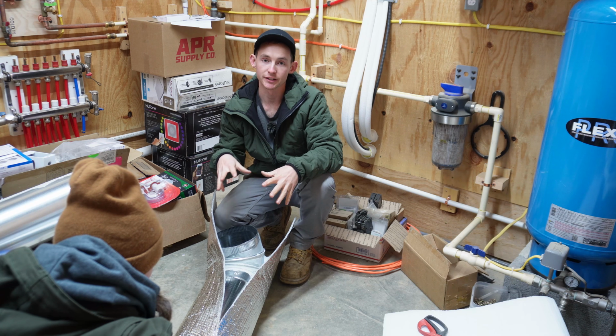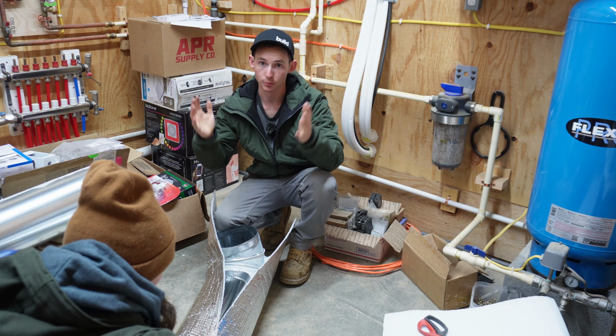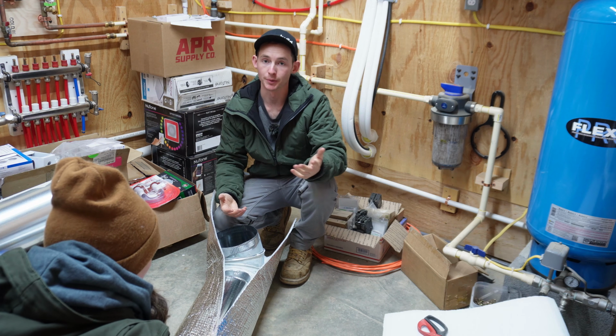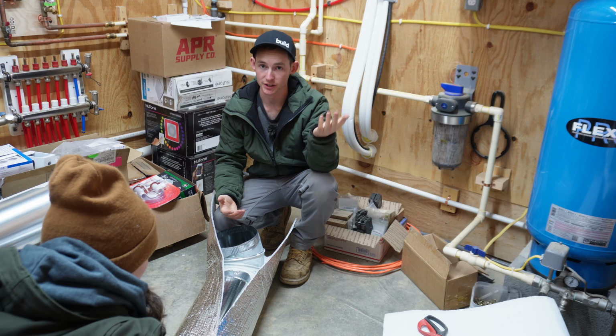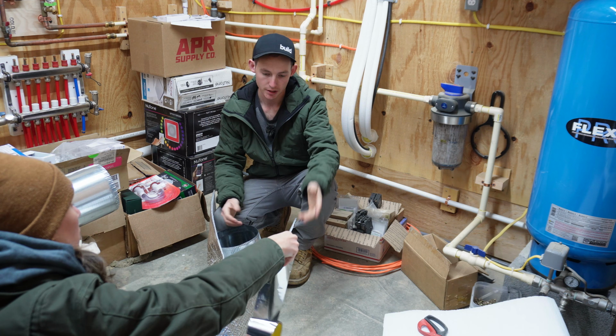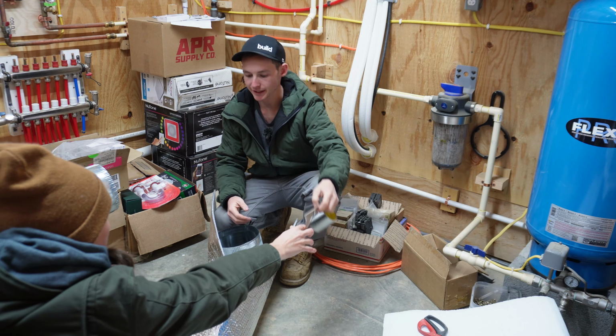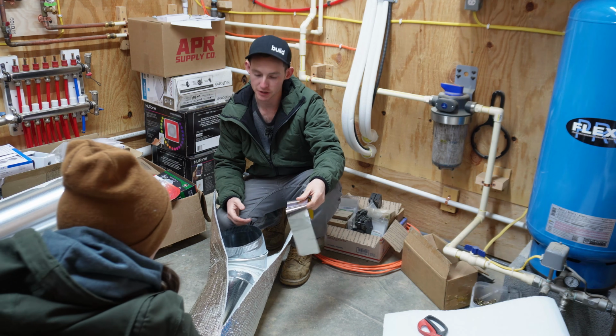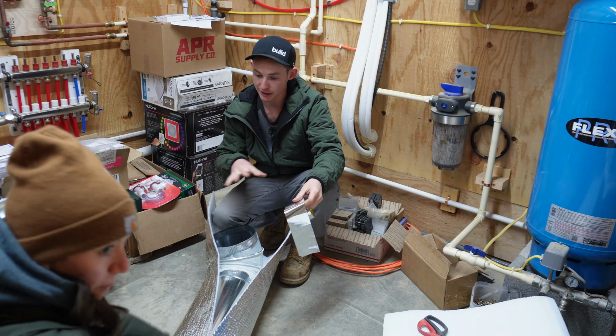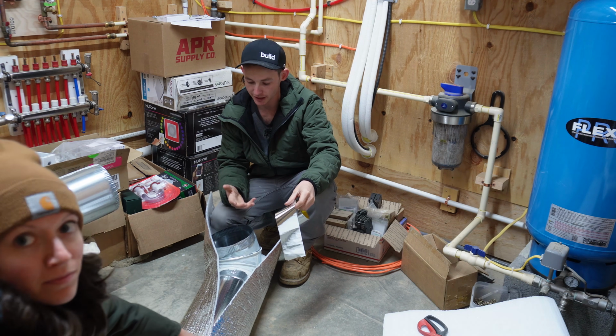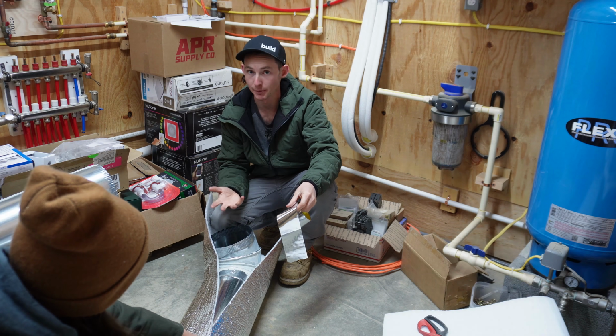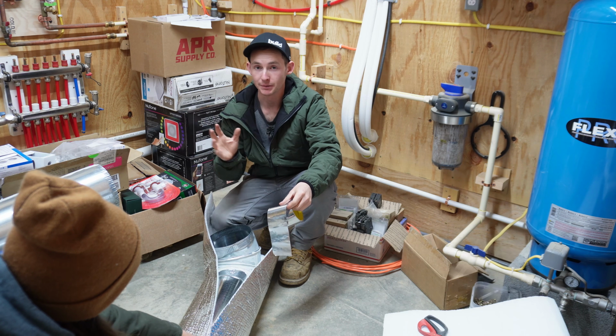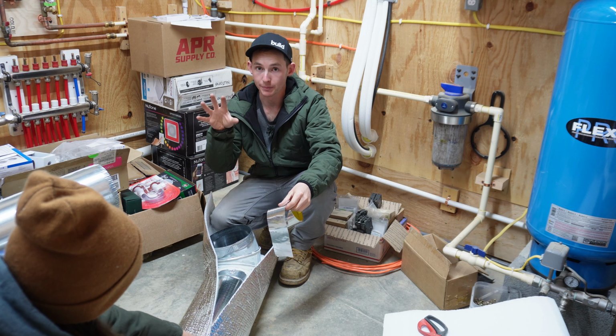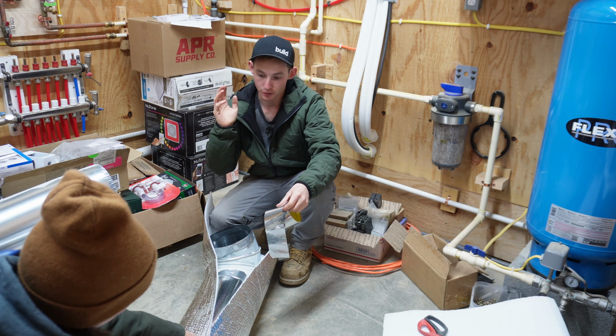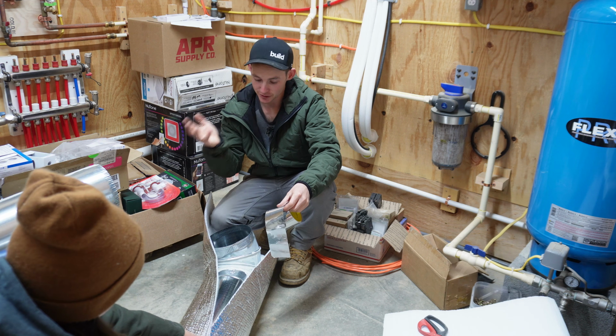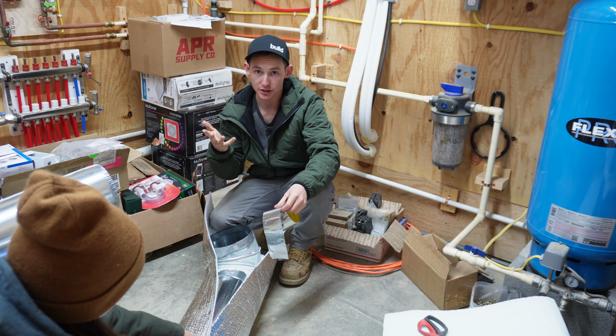These ducts are technically running in the conditioned envelope. We're going to be conditioning the garage to probably within 10 degrees of the living space above it year round, so I'm not too worried about a ton of heat loss through the ducts. But it's just best practice to avoid any potential condensation that might form in or outside the duct if there's a pretty big temperature and moisture difference. These will also be basically surrounded with rock wool batt in the joist cavities, so there's really not going to lose any sort of heat to the garage space.